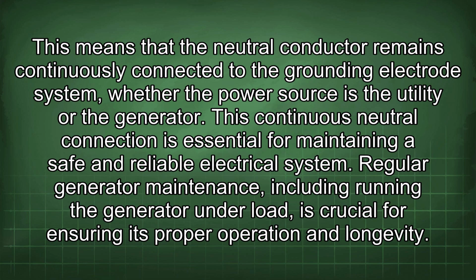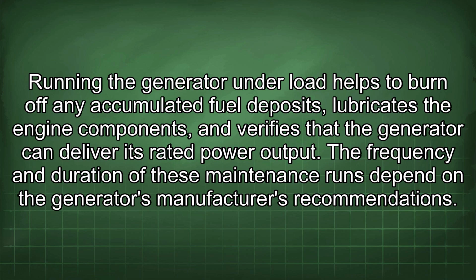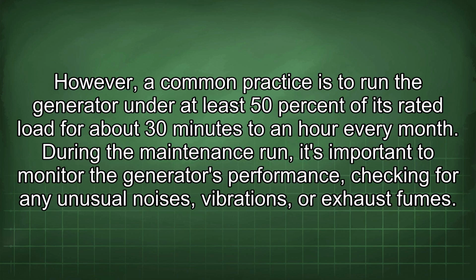Regular generator maintenance, including running the generator under a load, is crucial for ensuring its proper operation and longevity. Running the generator under load helps to burn off any accumulated fuel deposits, lubricates the engine components, and verifies that the generator can deliver its rated power output. The frequency and duration of these maintenance runs depend on the generator manufacturer's recommendations. However, a common practice is to run the generator under at least 50% of its rated load for about 30 minutes to an hour every month.